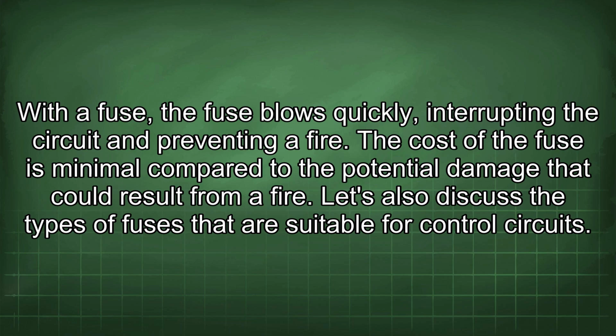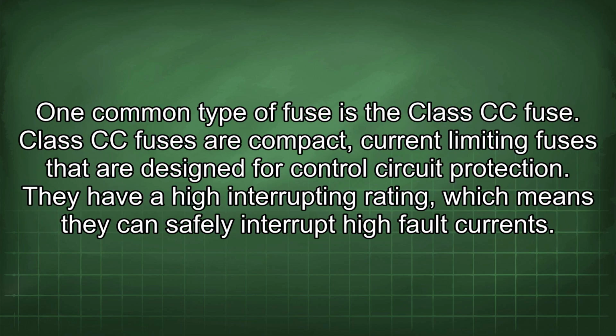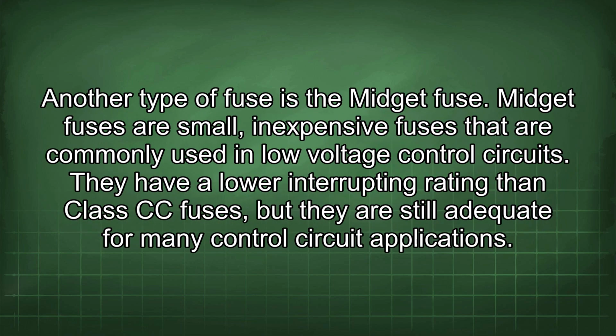Let's also discuss the types of fuses that are suitable for control circuits. One common type of fuse is the Class CC fuse. Class CC fuses are compact, current-limiting fuses that are designed for control circuit protection. They have a high interrupting rating, which means they can safely interrupt high fault currents. Another type of fuse is the midget fuse. Midget fuses are small and inexpensive fuses that are commonly used in low-voltage control circuits. They have a lower interrupting rating than Class CC fuses, but they are still adequate for many control circuit applications.